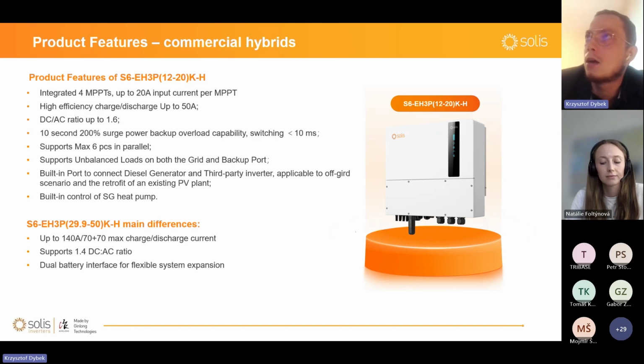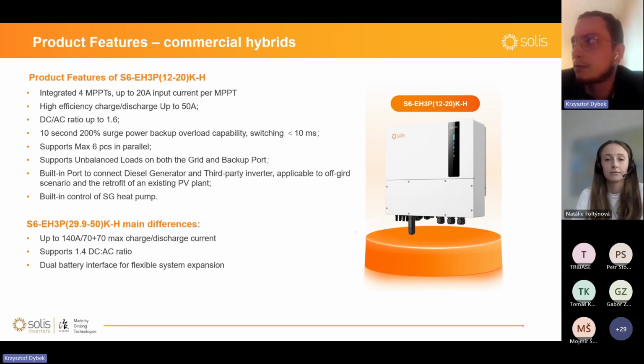DC-AC ratio is 1.6, which means the difference between wattage and the inverter capacity is called DC-AC ratio. I told you something about this when I talk about grid-tied inverters. So I forgot to mention what exactly this is. So inverter load ratio. You can put 32 kilowatts on DC side on 20K inverter. As ratio for this inverter is 1.6. This is if you have not good weather, for example. It's better to have always overloaded inverter.